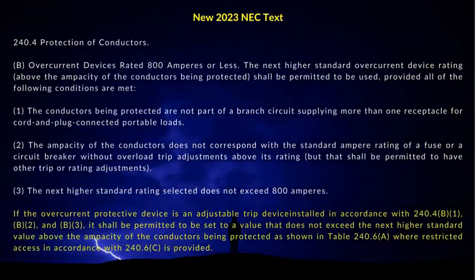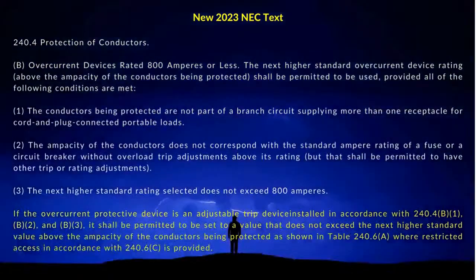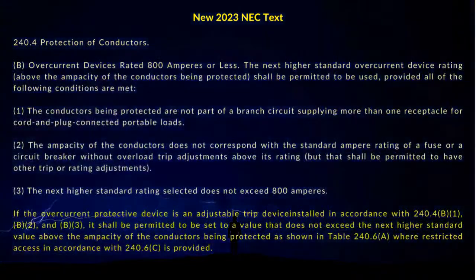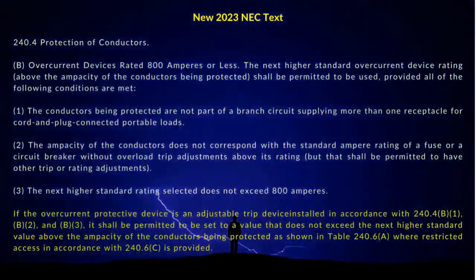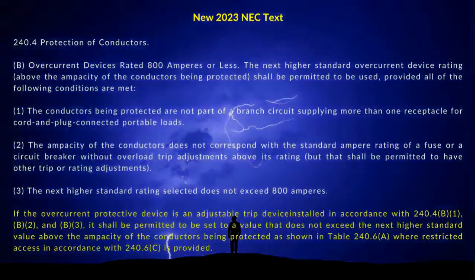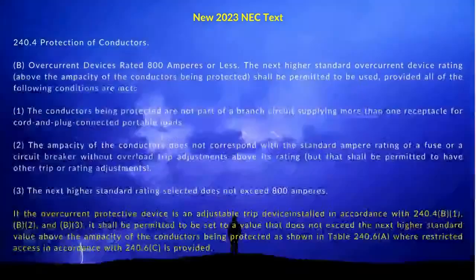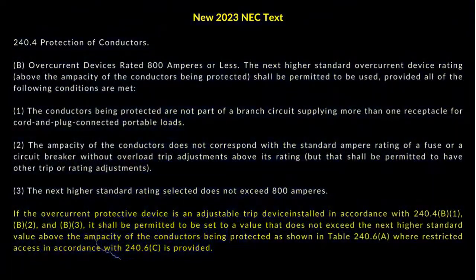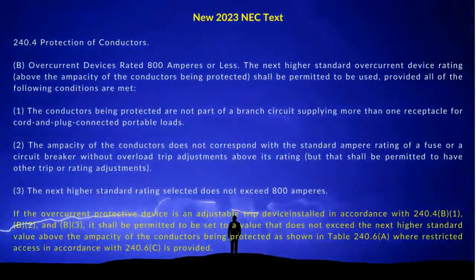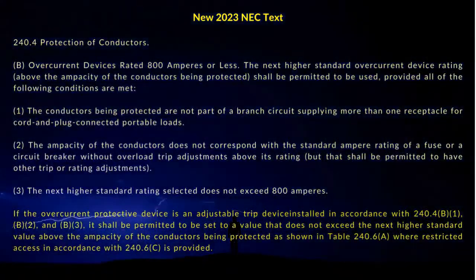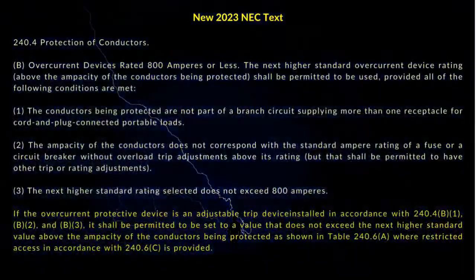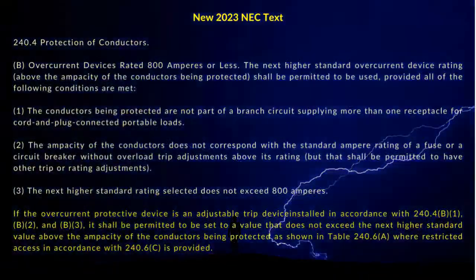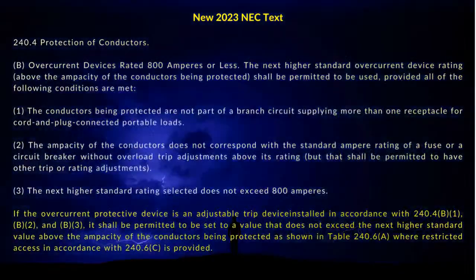If the overcurrent protective device is an adjustable trip device installed in accordance with 240.4(B)(1), (B)(2), and (B)(3), it shall be permitted to be set to a value that does not exceed the next higher standard value above the ampacity of the conductors being protected, as shown in Table 240.6(A), where restricted access, in accordance with 240.6(C), is provided.